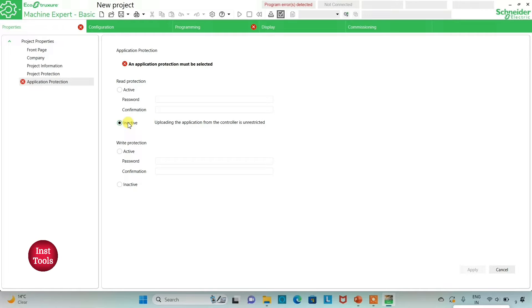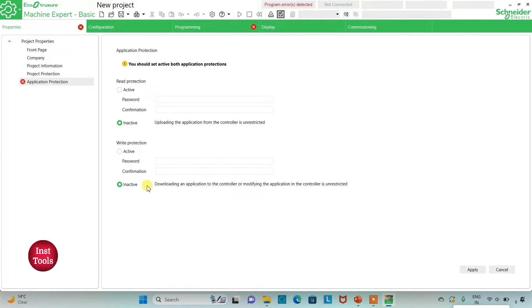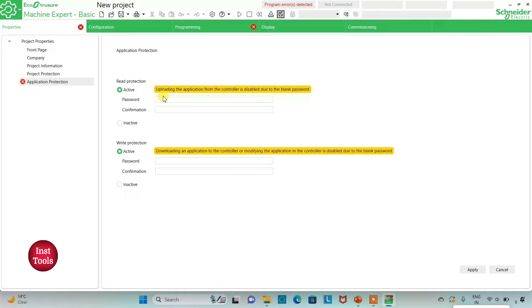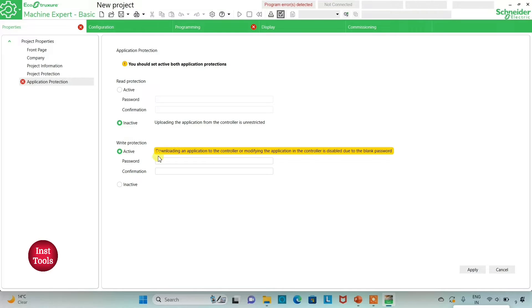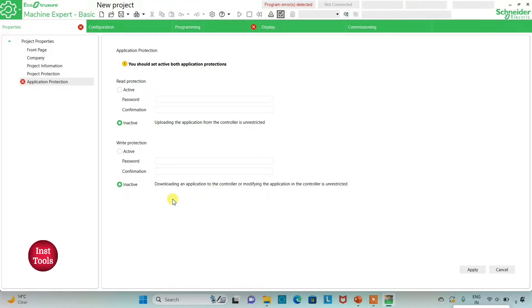I will keep read protection as inactive and write protection as inactive as well, so uploading and downloading the application from or to the controller is unrestricted. If I keep it active, uploading the application from the controller is disabled and requires a password, and downloading or modifying the application also requires a password. For now I will keep both read and write protection inactive.